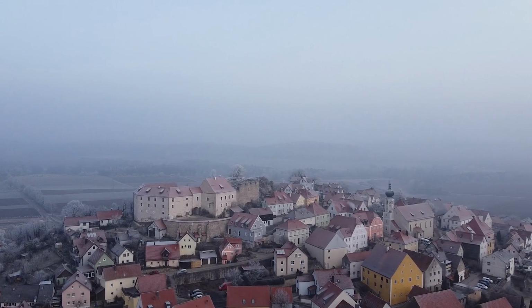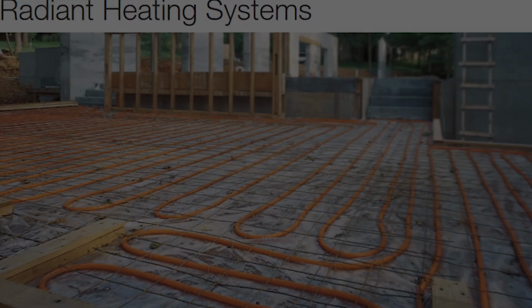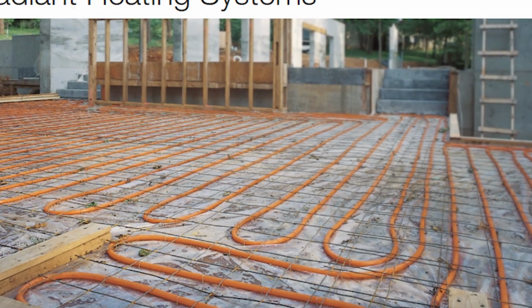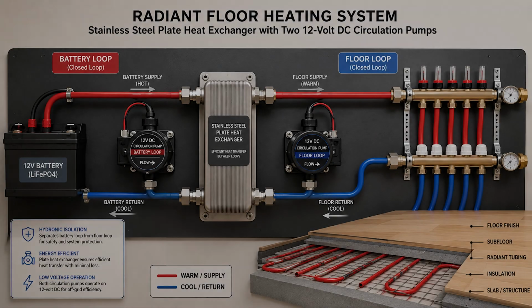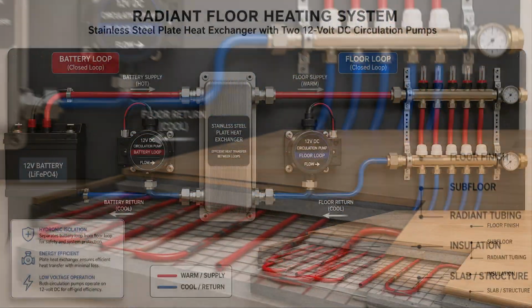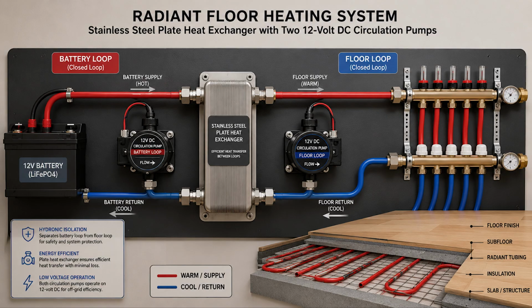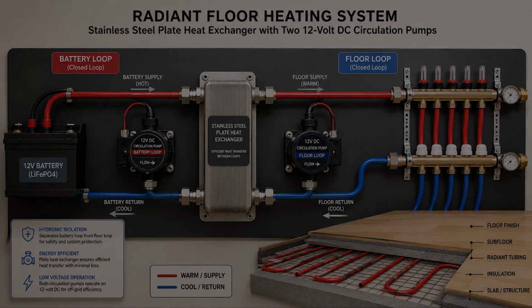Connecting to your home depends on your existing system. For radiant floor heating, use a stainless steel plate heat exchanger with 2 12-volt DC circulation pumps, one for the battery loop and one for the floor loop. These pumps can run on a small solar panel, keeping everything off-grid. For hot water baseboard heaters, use the same heat exchanger setup. For forced air systems, install a water-to-air heat exchanger in your air handler.